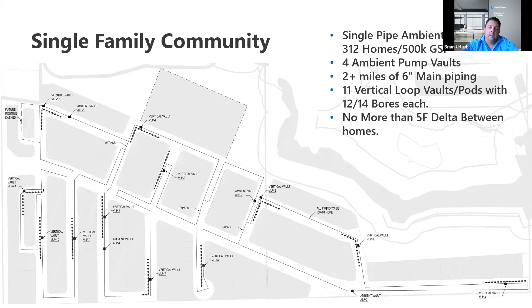This is an example of one that's been done—it's been in operation for over a year now, up in Canada in the Toronto market. There's 312 homes, a little over 2 miles of 6-inch main single-pipe ambient temperature loop, 4 pump stations to pump that loop, and 11 vertical pods of distributed vertical loops around the site to inject and reject energy in specific locations. It's been working great.